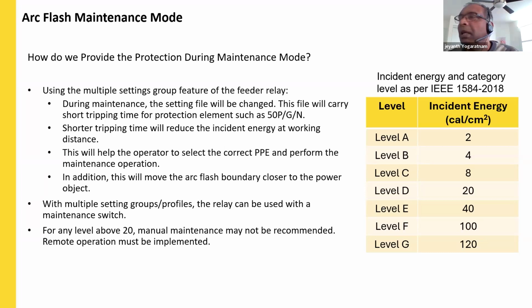So this can be minimized by adjusting the set point group so that we can come up with a setting which will expedite the tripping time when the fault comes. That will reduce the incident energy at the source, so that by having a proper PPE arrangement, the operator can get protected. If a device has multiple sources, if a device has the capability to work with multiple set point groups, you can have a second group for maintenance with a sensitive protection and a fast tripping time, which can be enabled during the maintenance and provide arc flash mitigation to the operator.